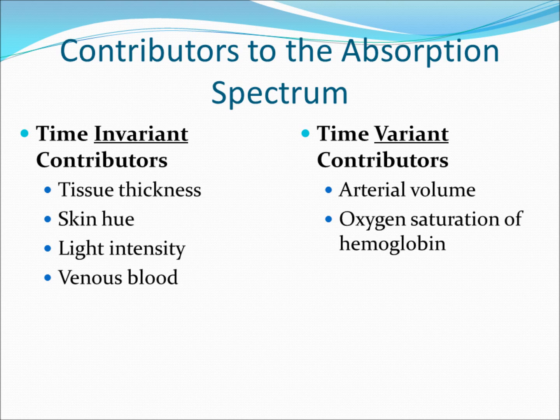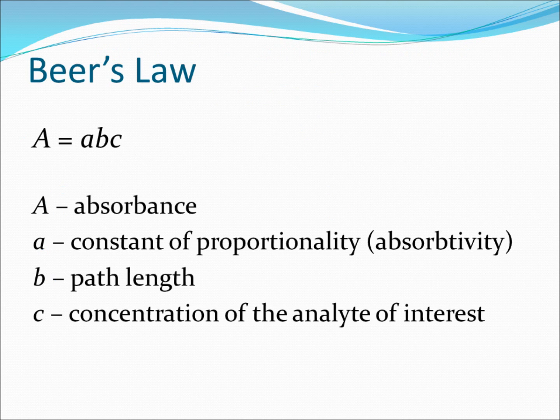The pulse oximeter is based upon Beer's Law, an empirical relationship that describes how three variables affect the absorbance of a substance. Beer's Law is a simple expression given by A = abc, where A is the absorbance, a is the constant of proportionality known as the absorptivity or the likelihood that a photon will excite a given molecule, b is the path length, and c is the concentration of the analyte of interest.